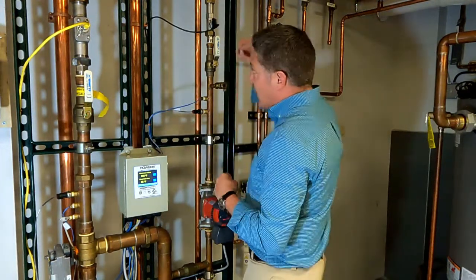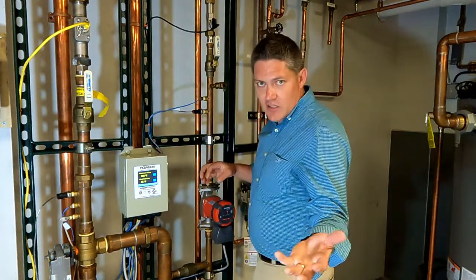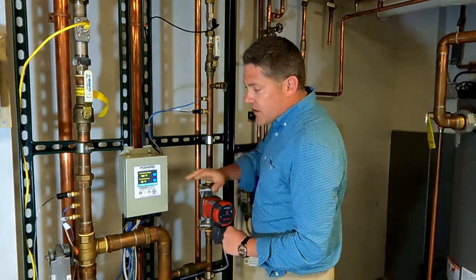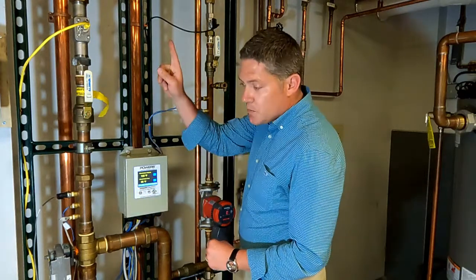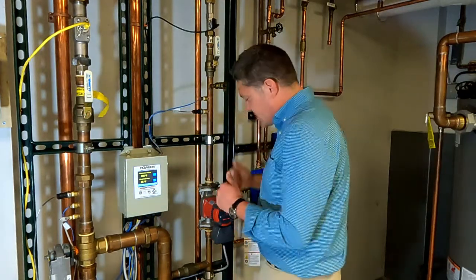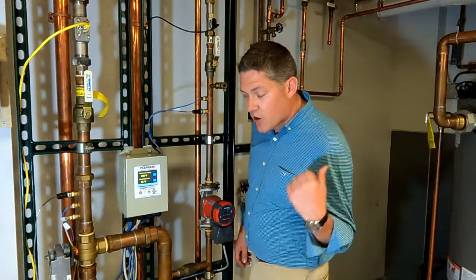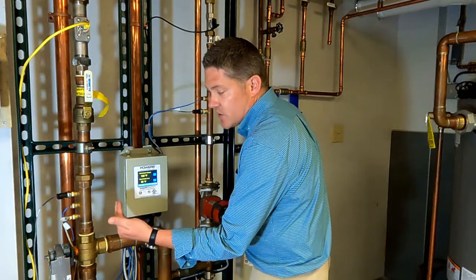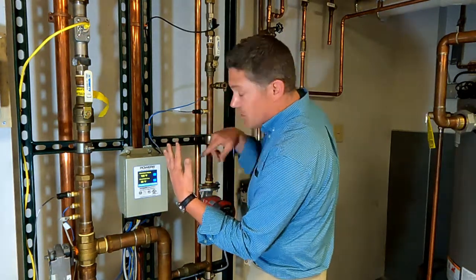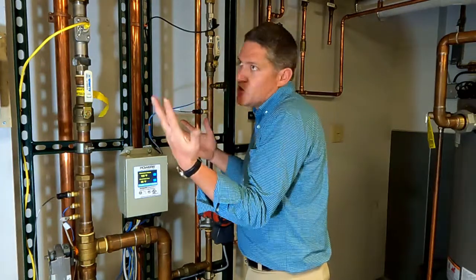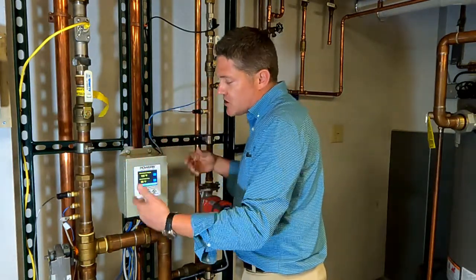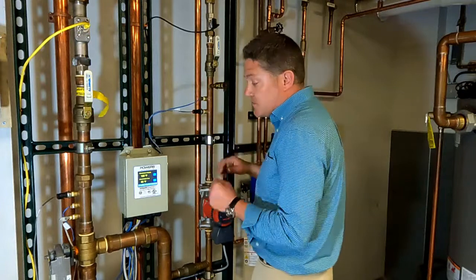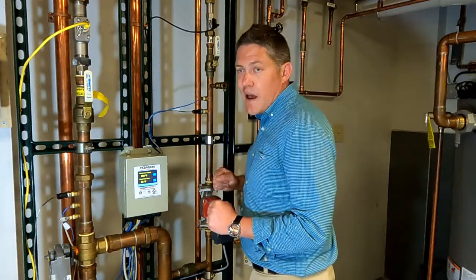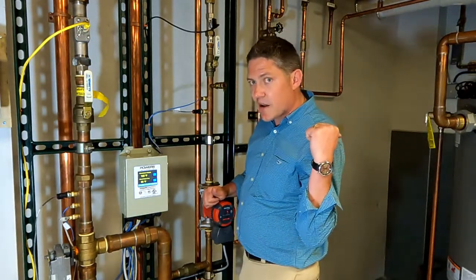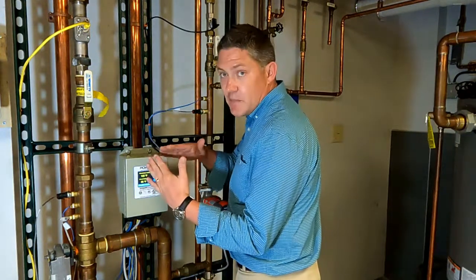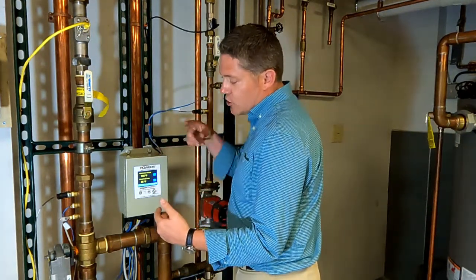So you have to split that. That return water comes back. If it lost 10 degrees, maybe you're putting about 90% of it back into the loop at the 110 degrees, and sending 10% of it back to the water heater to push that 160 degrees to blend in with the 110 from the recirc loop and bring you back up to your 120 degree desired outlet temperature. Maybe that percentage is less. Maybe 95% of it needs to go back, and only 5% needs to go back to the water heater to make up that heat loss on the loop.